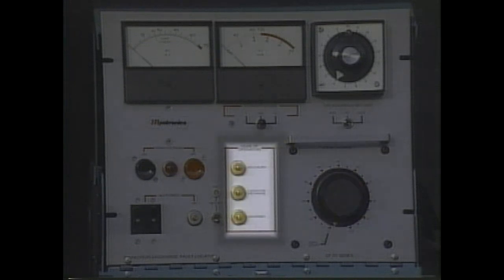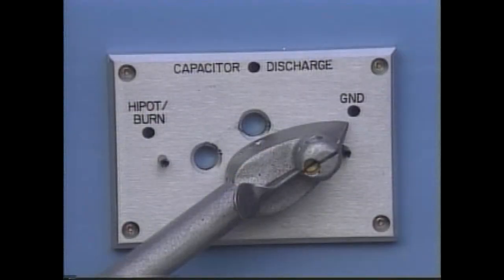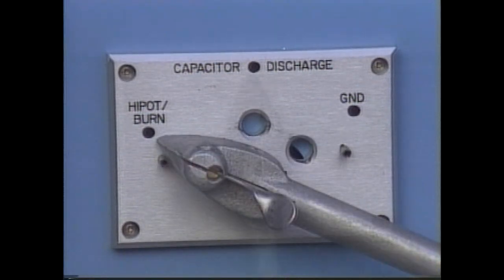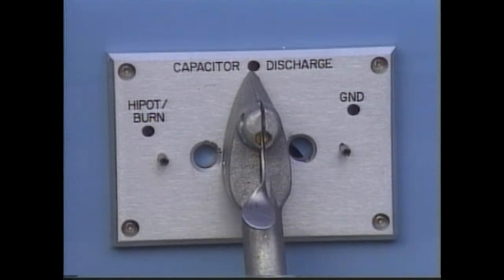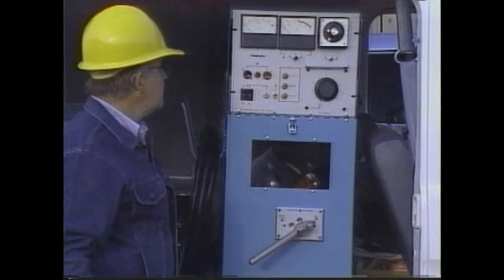There are 3 lights in a vertical row on the center of the thumper. These lights will tell the operator what mode of operation the thumper is set to. The last control on the front panel we want to talk about is the function control switch. This is the control that will adjust the thumper from a ground position to a burn or to a thump operation. When this switch is used, make sure the red high voltage switch is off. And whenever this switch is changed to any position, it should be set back to the ground position before it's set to the new position.